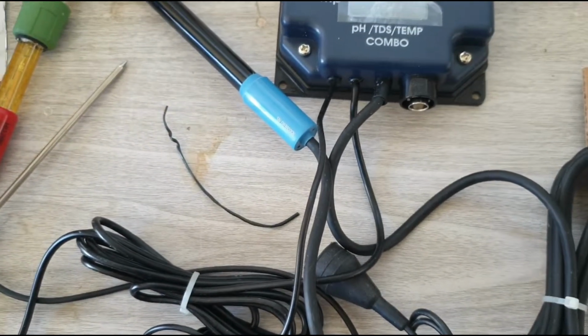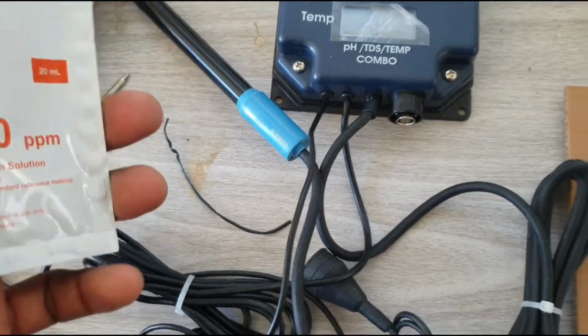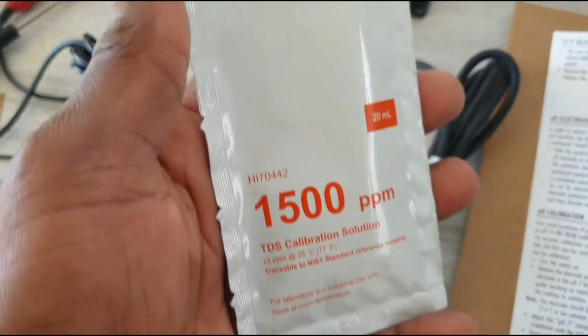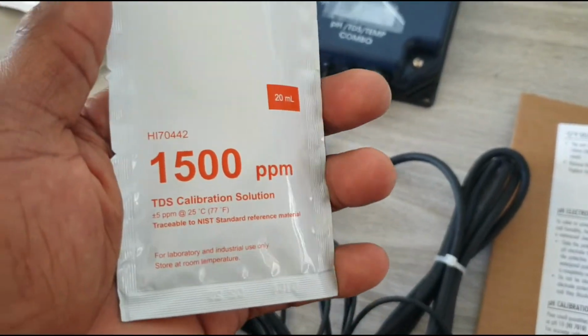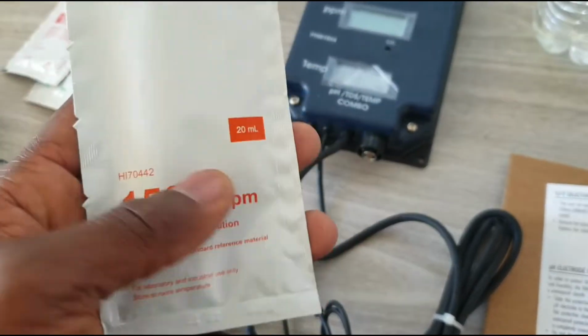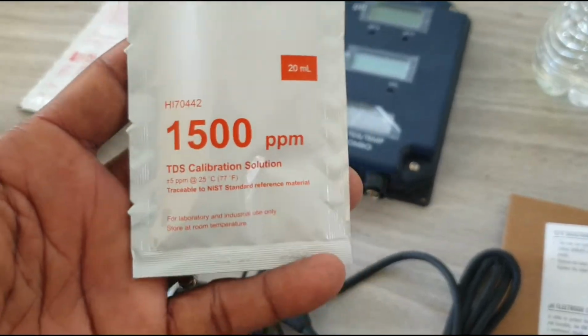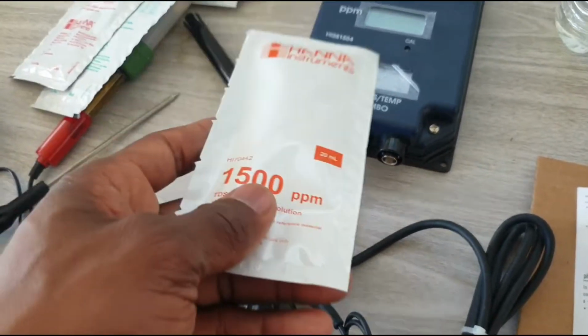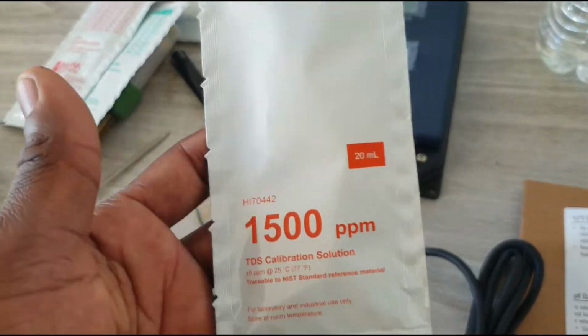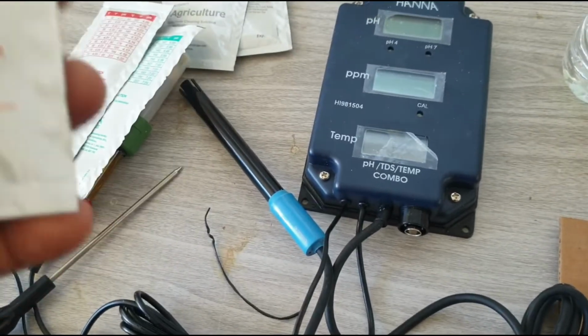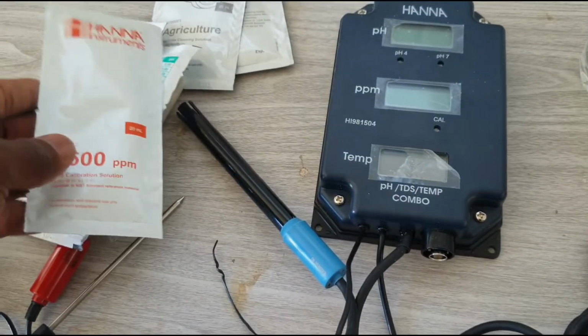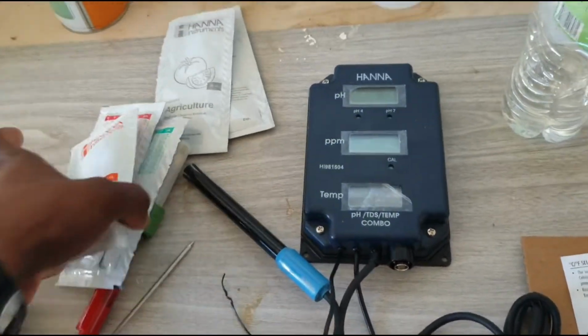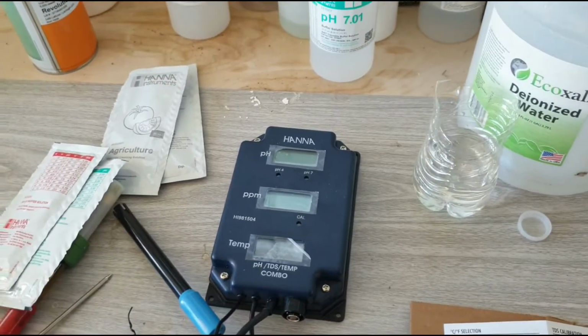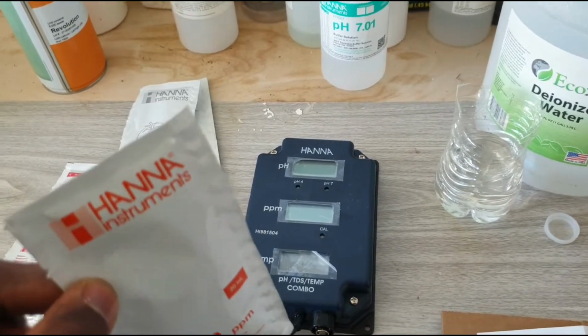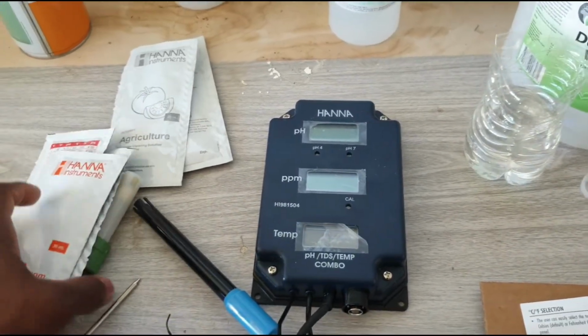So that is the calibration figure that we are going to use. And the good thing about what Hanna did is, instead of giving you both 1380 and 1500 calibration ppm solution, they sent the right one inside the packet. So they sent the 1500, which corresponds to the code of this meter. They basically send what you would use. So let us get into calibration now. We're just going to tear the packet, wash the probe off and dip it inside the packet, so we don't have to pour anything into any beaker.